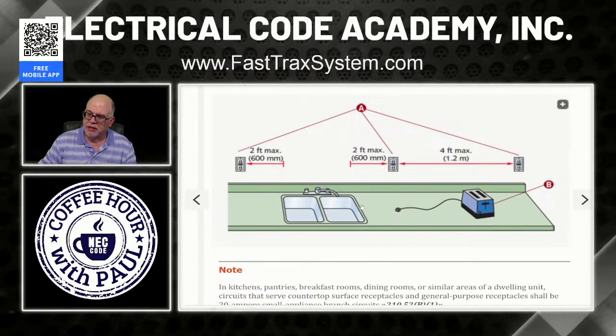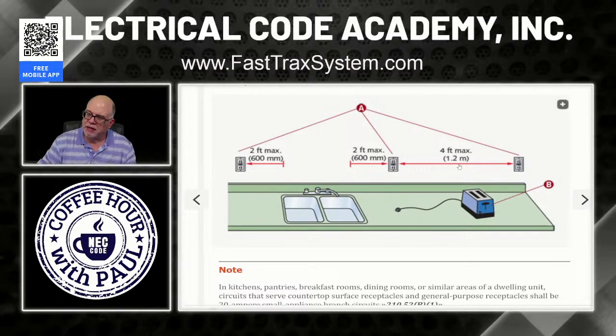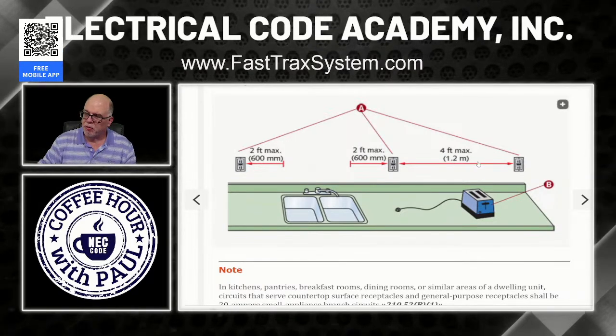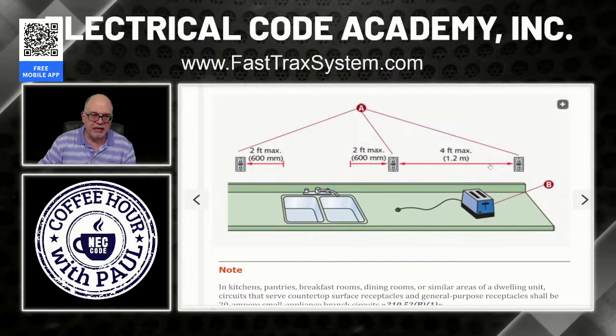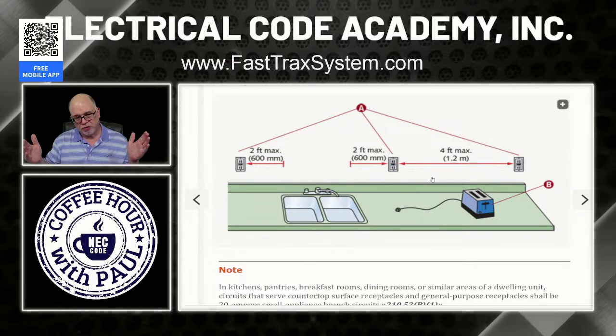So anything put here would be able to reach it. Anything put here would be able to reach it. And then the maximum distance between the receptacles would be 4 feet. Because if I put this toaster right here in the middle, it's going to be able to reach this receptacle or this receptacle. If I move it closer to this side of that 4 feet, then it can't reach this one, but it most certainly can reach this one. So that's why we have something called the 2 foot, 4 foot rule. Okay.